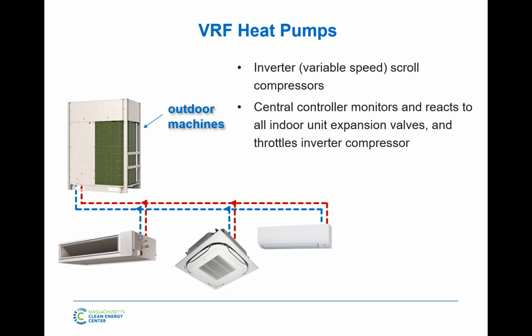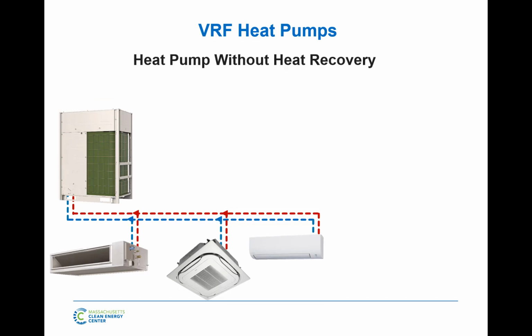And that becomes important in the conversation later. So VRF is pretty good at full load. It'll beat most things, but part load is where the magic really happens. The IEER, I'll go over that later. The IEER is a weighted average of the efficiency of the system at 100%, 75, 50, and 25. So it counts your full load for 1%, it counts your 75% load for 30%, your 50% load for 40%. It's a weighted average based on average hours that a building spends at different loads. So it's a standard across the board. So it's a mix of those.